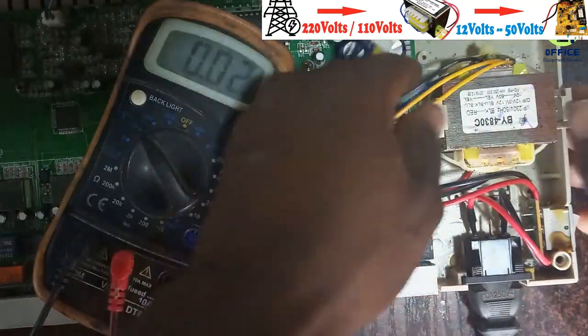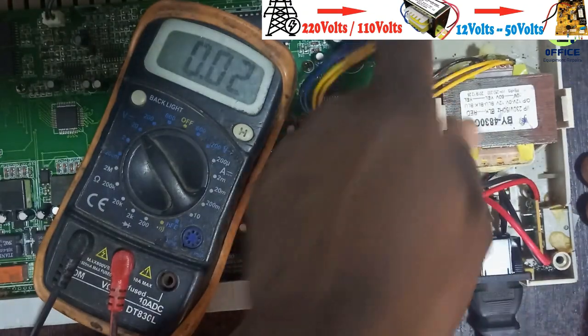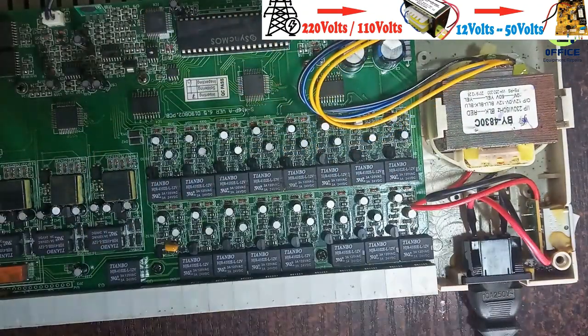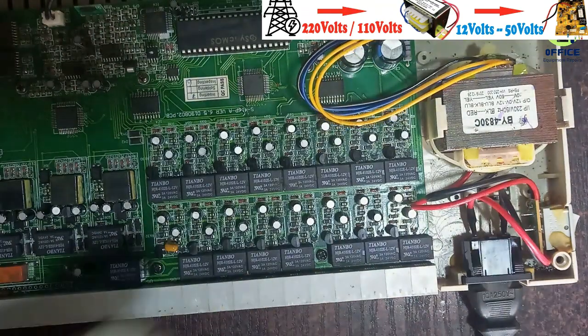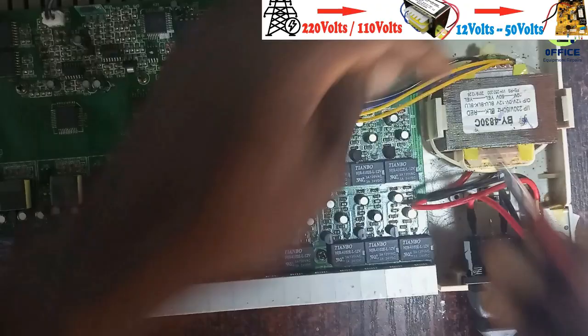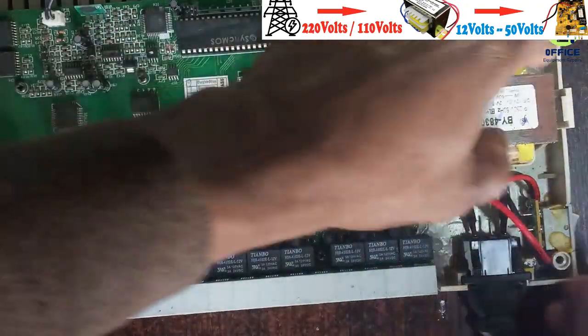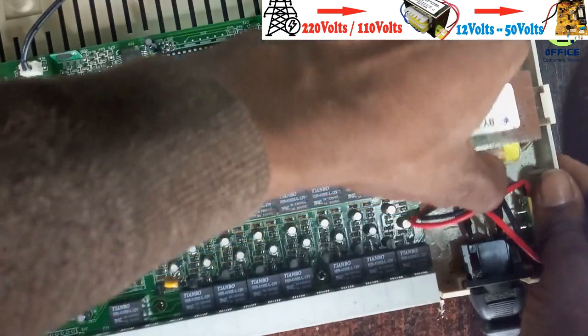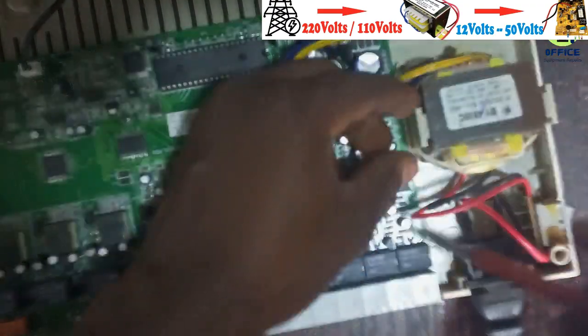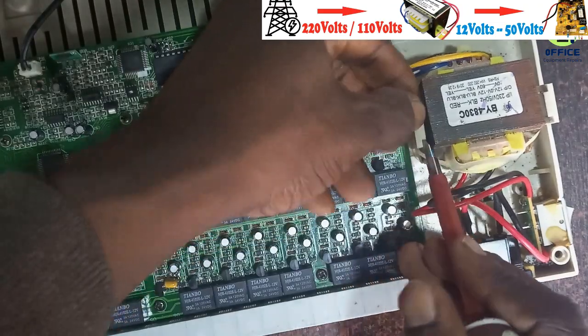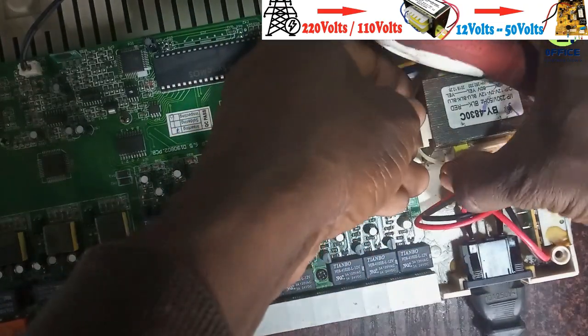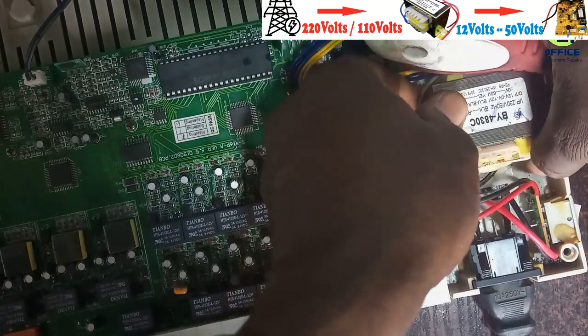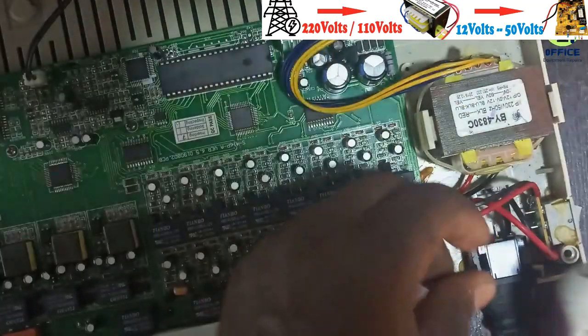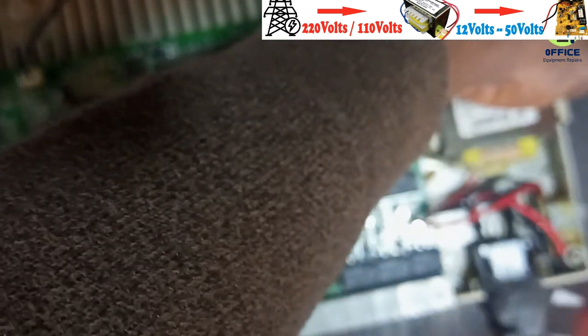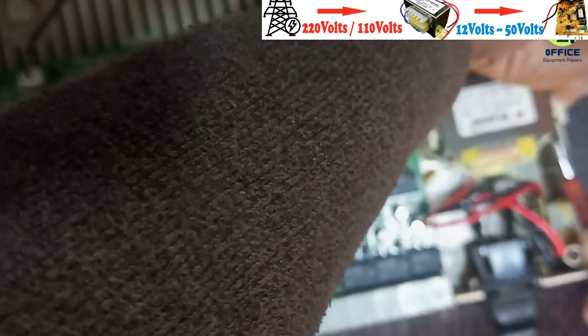So what we're going to do is remove this transformer. A few things you can do to fix a transformer: number one, rewind it, I can repair it, or if you have the opportunity of getting another one, you can just get another transformer, but it has to be this exact transformer rating. If it is not this exact rating, it might burn your board, and then you now have a bigger problem: the board is gone and the transformer is bad.